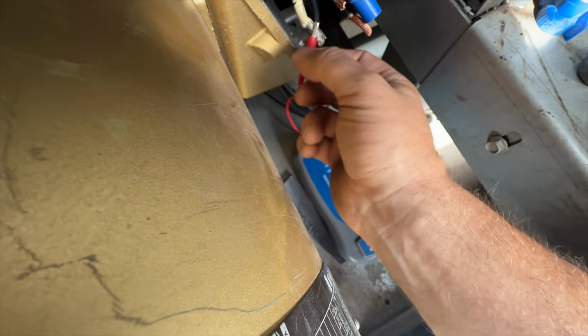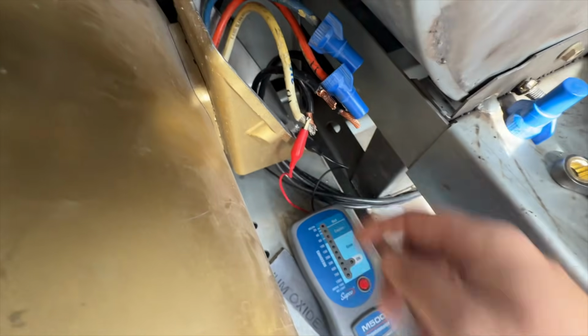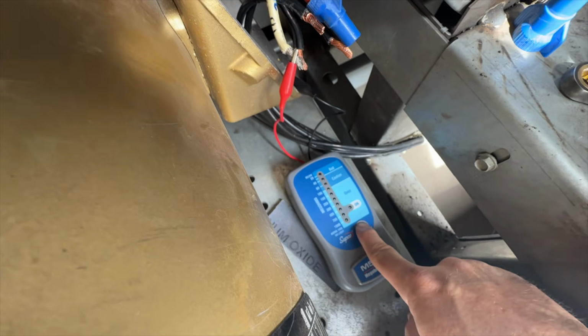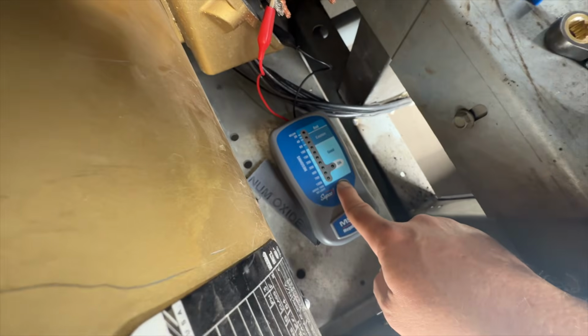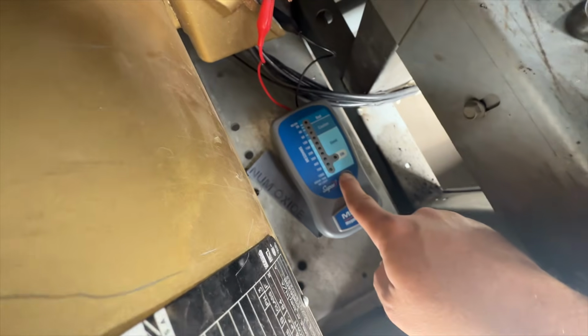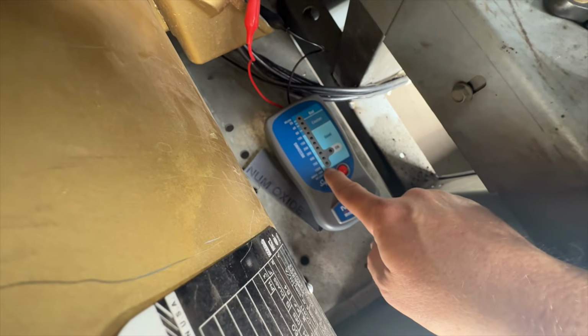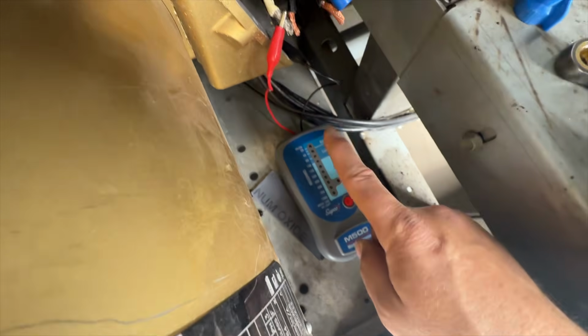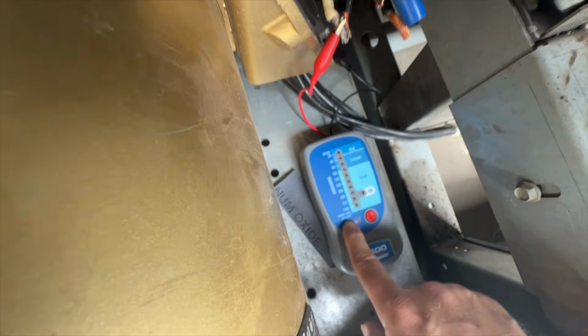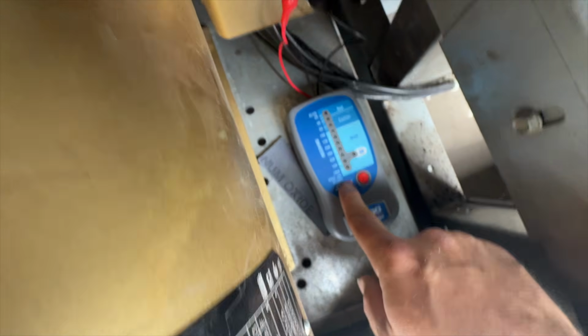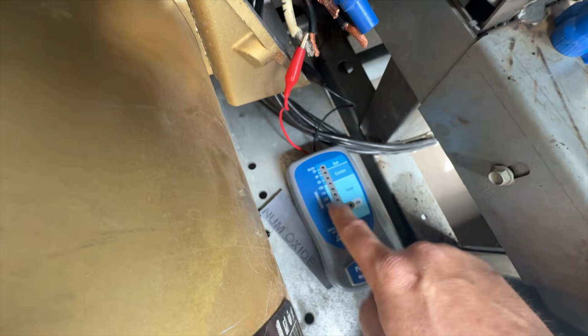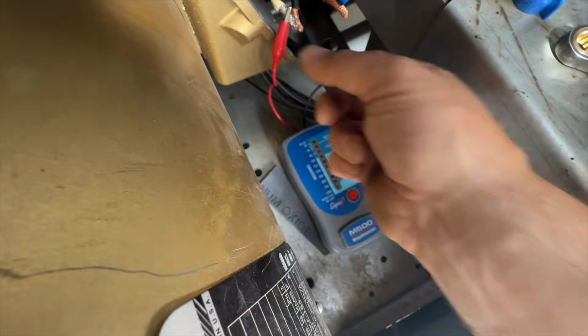So I'm going from line 3 to ground. I push and hold this for 10 seconds. Okay, the on light is on, and the reason why it went off is because, you can see here it says above 1,000 mega ohms, there's no light. So this is past the highest it goes. So we can go ahead and check all 3 of these.